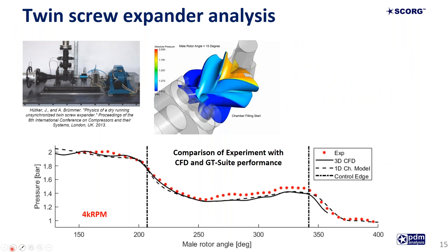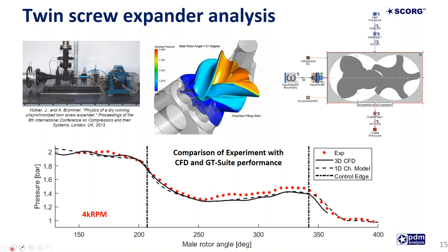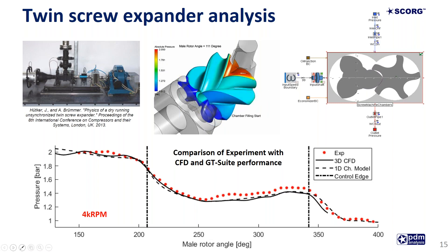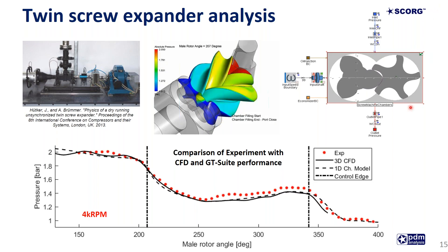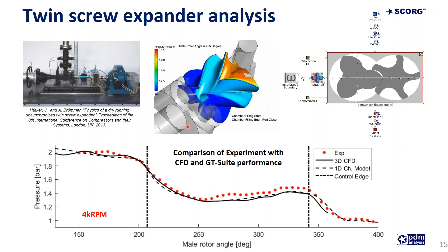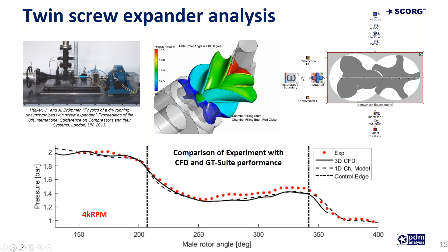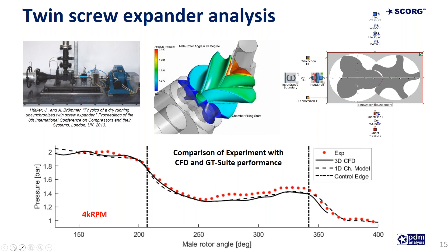Another case study was done on a twin screw expander. SCORG alongside GT Suite are capable of calculating the performance of expanders and their systems, such as an organic Rankine cycle with refrigerant or air as a working fluid. The results obtained using SCORG and the GT Suite 1D chamber model were compared with CFD analysis prepared with SCORG and ANSYS CFX solver, and with experimental data recorded at Dortmund University. Both simulations align very well with the measured data, demonstrating the versatility of SCORG for performance prediction and optimization of screw machines.